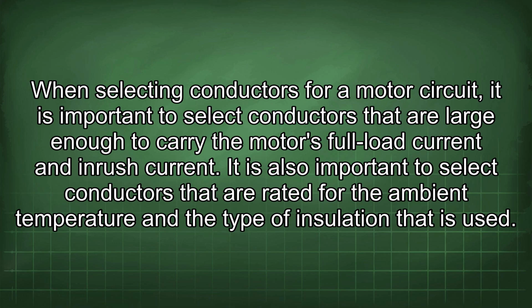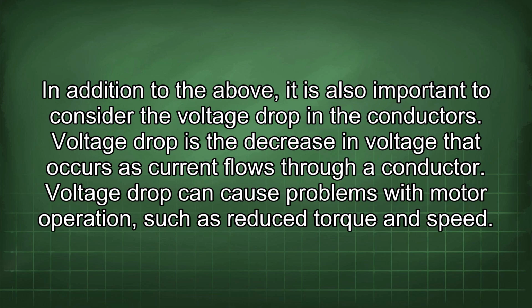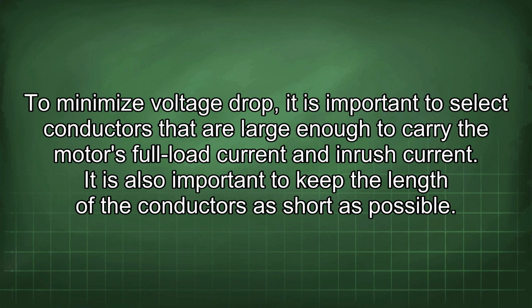In addition to the above, it is also important to consider the voltage drop in the conductors. Voltage drop is the decrease in voltage that occurs as current flows through a conductor. Voltage drop can cause problems with motor operation such as reduced torque and speed. To minimize voltage drop, it is important to select conductors that are large enough to carry the motor's full load current and inrush current. It is also important to keep the length of the conductors as short as possible.